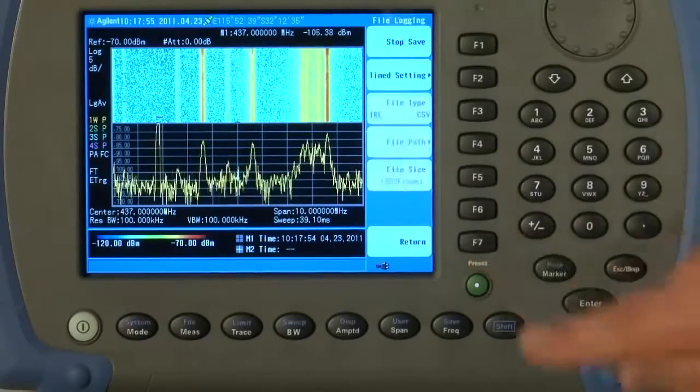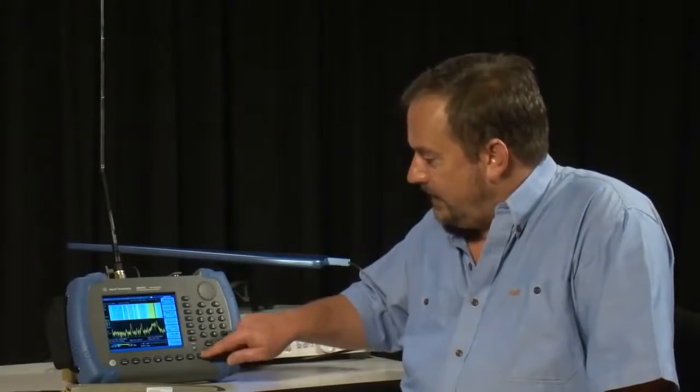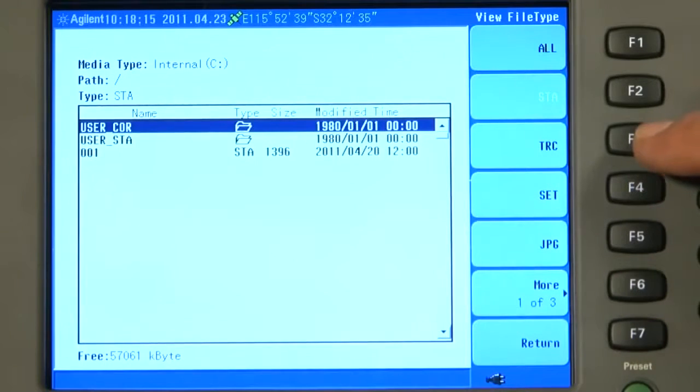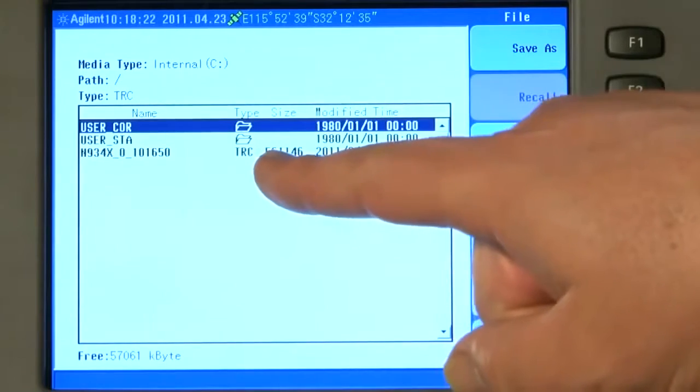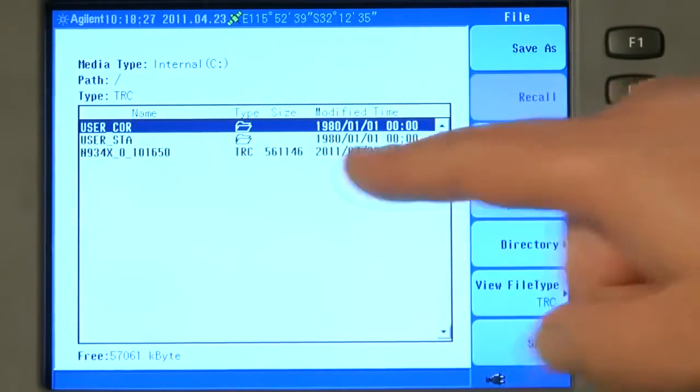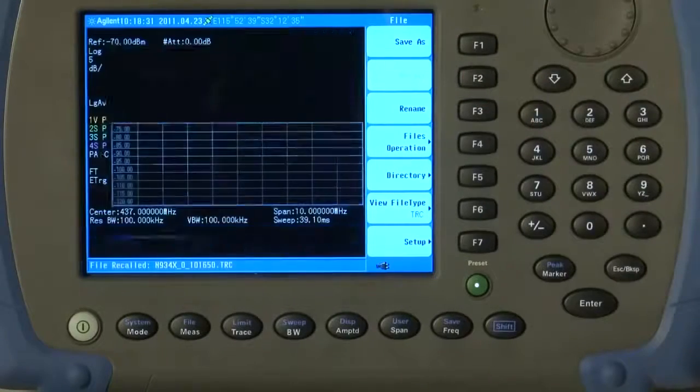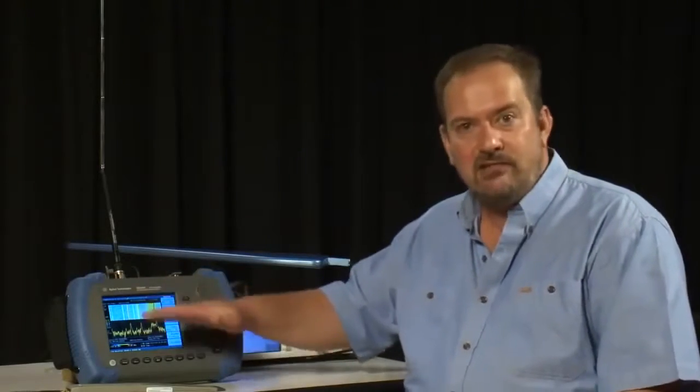I will press Return. If I now press Stop Save and press Shift File, and let us view Trace Data, you will see here the TRC, the trace file, that the unit has stored for the spectrogram logging. Here, stored at 20 past 10 in the morning on the 23rd of April. So, if I scroll down to that and press Recall, now I have called back onto the screen the entire spectrogram trace log that we have just recorded.